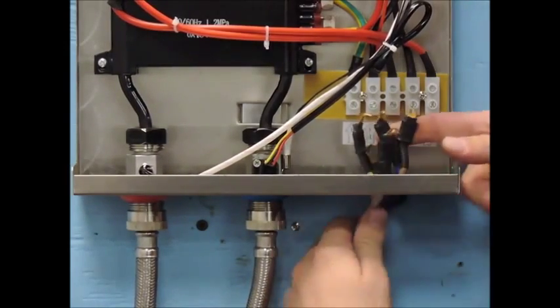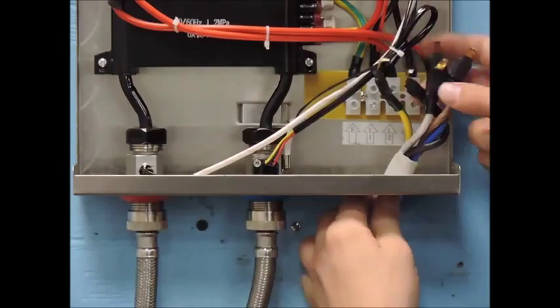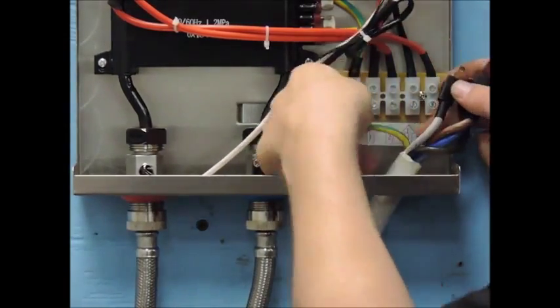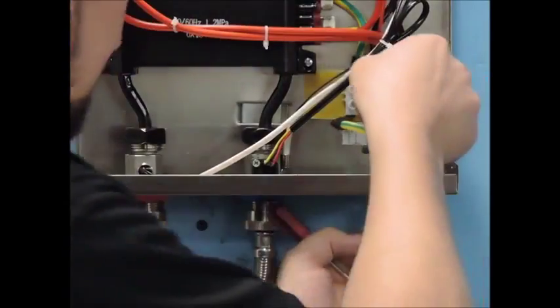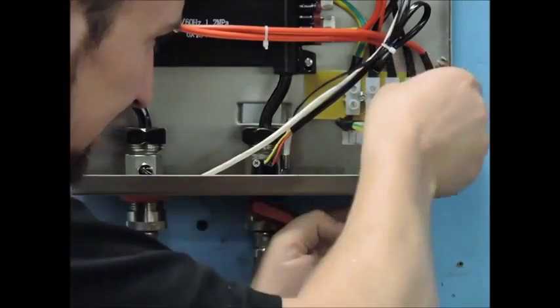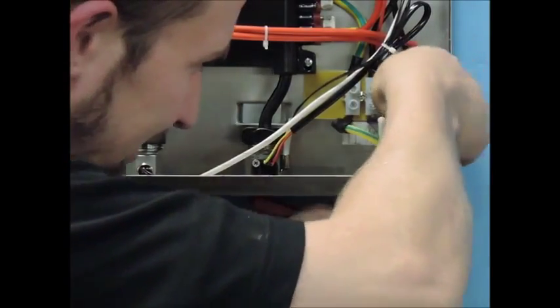In this video, we will wire the eco-180, and we are using a specialty cable to make the explanation easier to understand. The port in the terminal block to the farthest left is the terminal for your ground wire, labeled E, and should terminate at the grounding bar in the breaker panel.